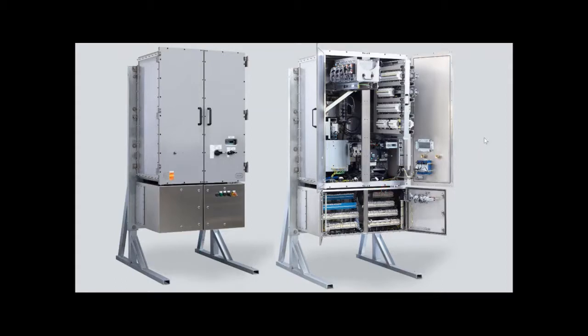And we have made a heat run test in our laboratory on the crane. We have tested also in real conditions with real load on the crane, and stated together with the customer the rated diversity factor, for example. That's what made it possible for us to install everything inside one cabinet.